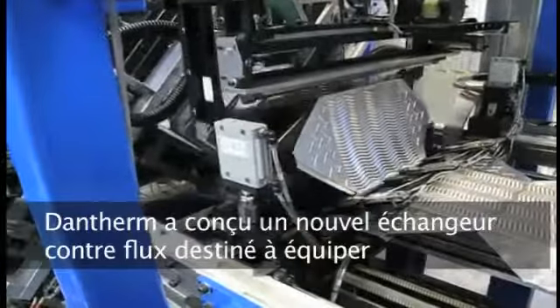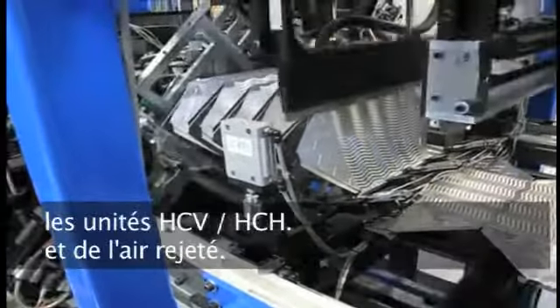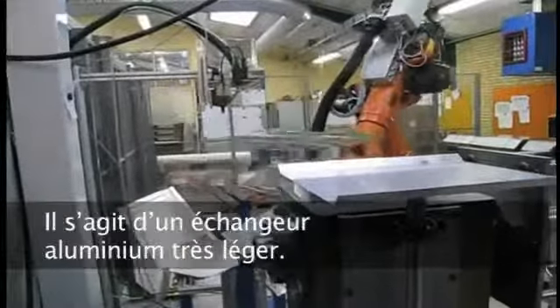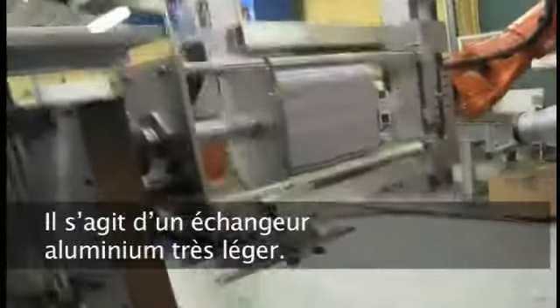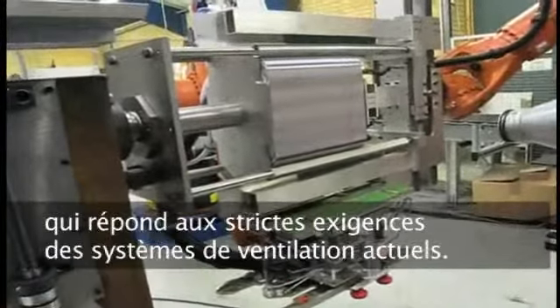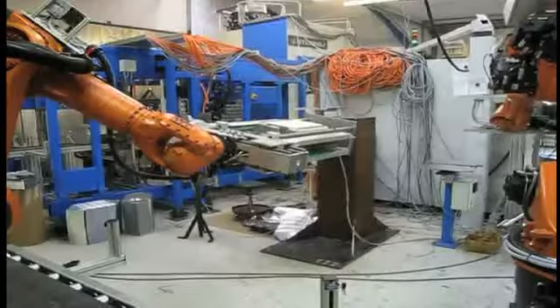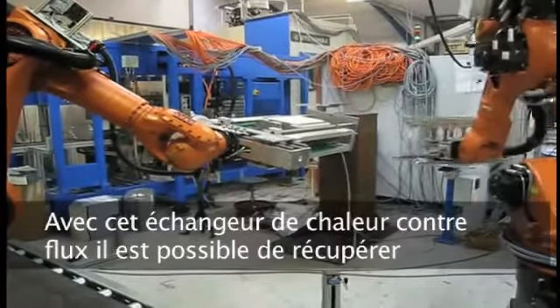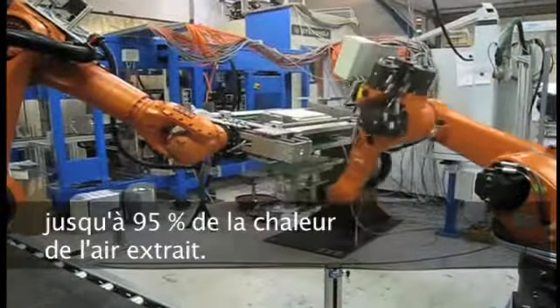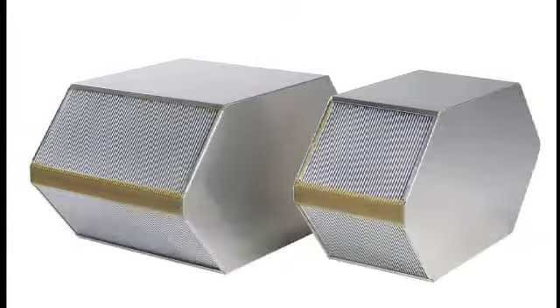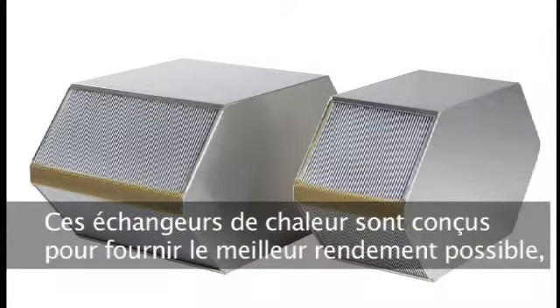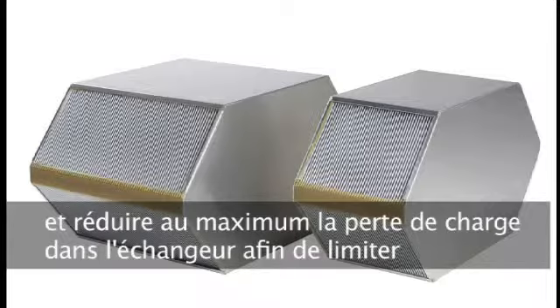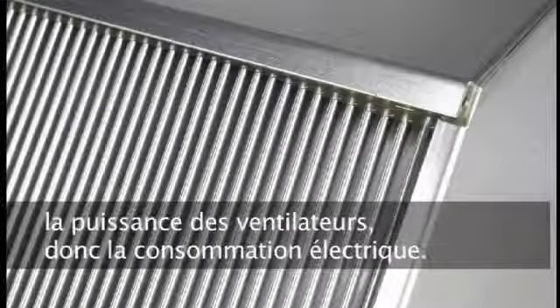Dantherm has developed a sophisticated robot-operated production facility to manufacture their own lightweight aluminium counterflow heat exchanger that meets the high demands of modern and up-to-date ventilation systems. The counterflow heat exchanger recovers up to 95% of the heat from the extracted air. The heat exchangers are tailored to provide the highest possible efficiency with the lowest possible pressure loss at air volumes used for ventilation in dwellings.